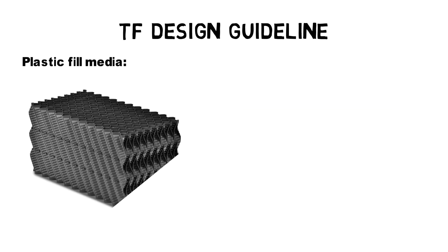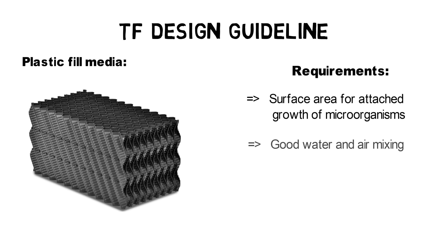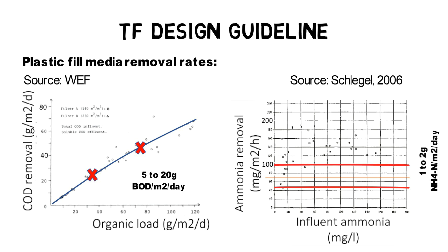The plastic-fill media layers must provide enough surface area for attached growth of microorganisms, ensure good water and air mixing, as well as withstand structural loadings. Typical removal rates for trickling filters are between 5 and 20 grams BOD per square meter of plastic-fill media surface area per day, and 1 to 2 grams of ammonia per square meter per day. Plastic-fill media is available in different types with various specific surface areas — the higher the surface area, the more microorganisms are available and the better the performance of the trickling filter, but at the same time the higher the risk of clogging.